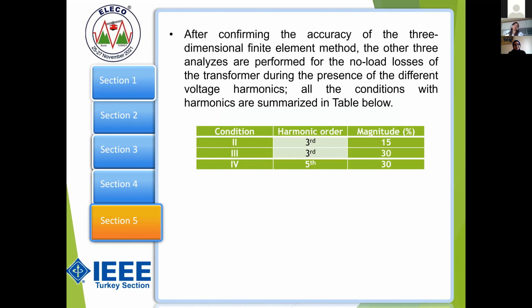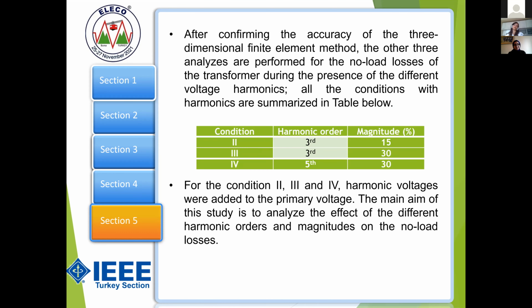After confirming the accuracy of the three-dimensional finite element method, we analyzed three more conditions that are given in this table. In the first and second conditions, we added 15% of the third harmonic. In the third condition, we added 30% of the third harmonic. In the fourth condition, we added 30% of the fifth harmonic. We added the harmonic voltages to the primary voltage to see the no-load losses of the transformer. The main aim of this study is to analyze the effect of different harmonic orders and magnitudes on the no-load losses.